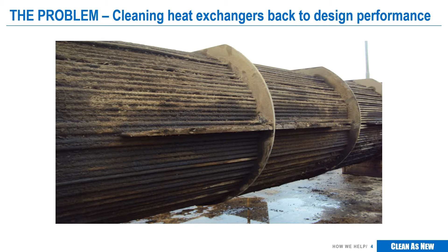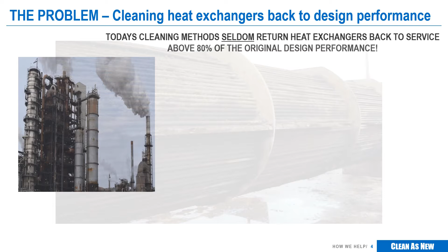As we all know, the fouling of heat exchangers reduces plant efficiency, and one of the biggest maintenance challenges the industry faces is the removal of this fouling and restoring plant performance. Unfortunately, today's cleaning methods seldom return heat exchangers back to service above 80% of the design specification.